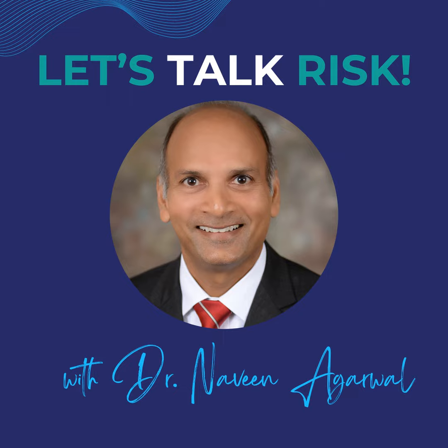Which makes perfect sense. I kind of call it the easy way of doing it because it doesn't necessarily require you to think. But what I looked at is trying to flip that backwards a little bit. Reliability is really a core functional characteristic of the product, so it should sit at the design inputs and then link directly over to your risk analysis. So ideally, you have a design reliability number as part of your design inputs, and then that number should directly come out within your DFMEA as well, because that's really a core function of how well the device functions and what it can do.